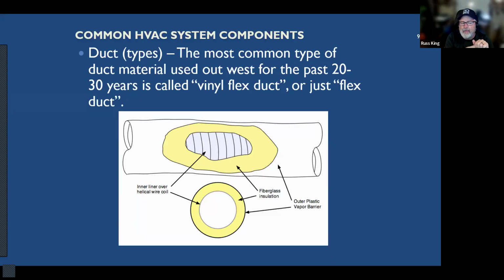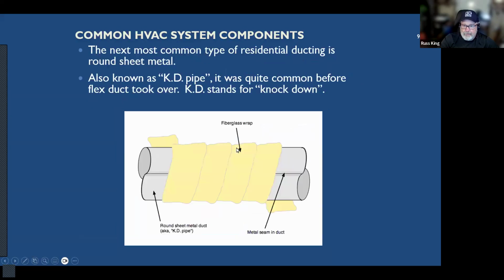Not such a big deal in our climate. We live in a pretty dry climate, but like in Florida where it's super humid, if you don't have a vapor barrier on the outside, what happens is this moist attic air will migrate through the insulation, and when it comes in contact with that cold duct on the inside, moisture condenses and it runs down to the bottom. It'll drip out the bottom and put stains in your ceiling. All right. Or worse, cause your ceiling to collapse. But so they put this plastic bag around the outside of it to keep that moist air from coming inside. We call it a vapor barrier. But in our climate, the only purpose it serves is to hold the insulation in place. Okay. But flex duct, very common.